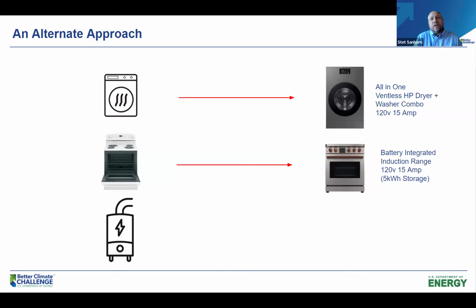It's also giving you almost a day's worth of cooking before that battery is totally drawn down. So you have that resilience built in. Those two things alone, when we go back and look at the electrical sizing calculation, now bring us back under that 60 amp for most apartments in most climate zones. And so it's a key way of saying, well, do I want to do the disruption of ripping out my entire systems in my building, or are there alternate solutions that actually keep me within the capacity limitations that I already have?